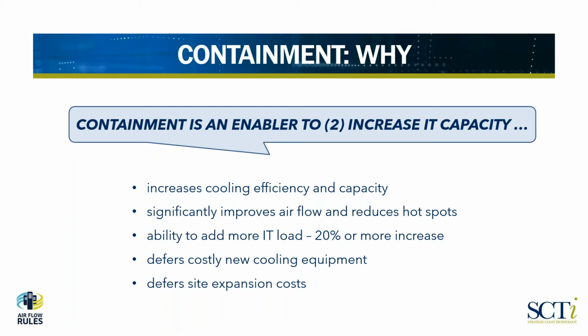If you look at the chart that we had up earlier with regard to rack densities, you see containment kicking in around 5 or so kilowatts. If you're doing containment and doing it properly, there's no reason why you can't push that up to 12, 15 kilowatts per rack, and in some cases even higher. As you get higher, you've got to be more cautious with it, but certainly 12 to 15 is a reasonable level for increasing the rack densities.